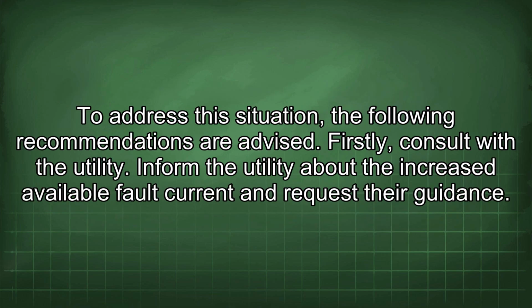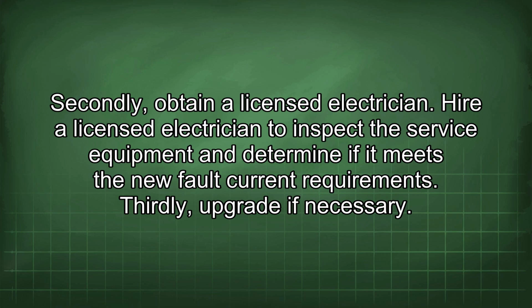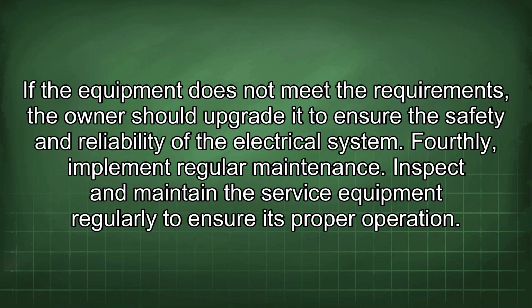To address this situation, the following recommendations are advised. Firstly, consult with the utility. Inform the utility about the increased available fault current and request their guidance. Secondly, obtain a licensed electrician. Hire a licensed electrician to inspect the service equipment and determine if it meets the new fault current requirements. Thirdly, upgrade if necessary. If the equipment does not meet the requirements, the owner should upgrade it to ensure the safety and reliability of the electrical system.